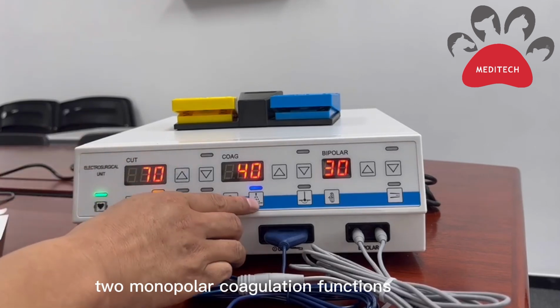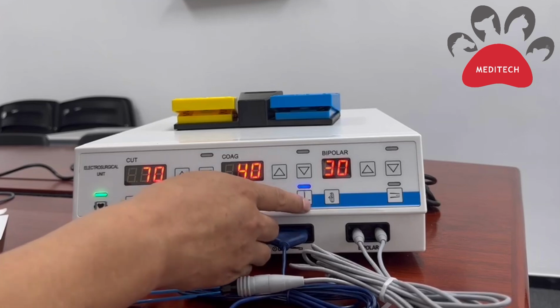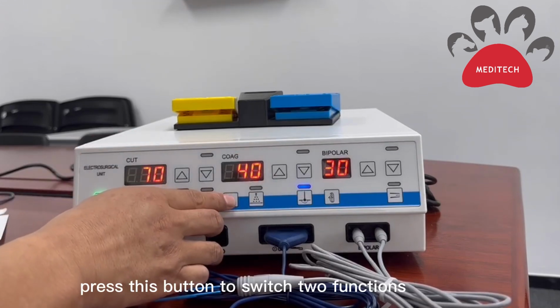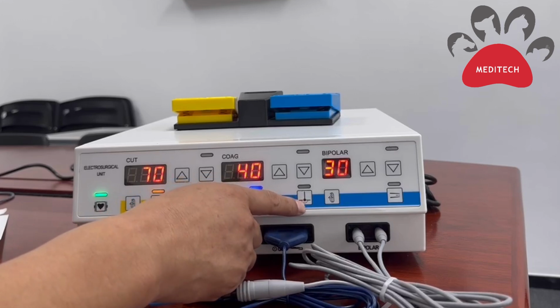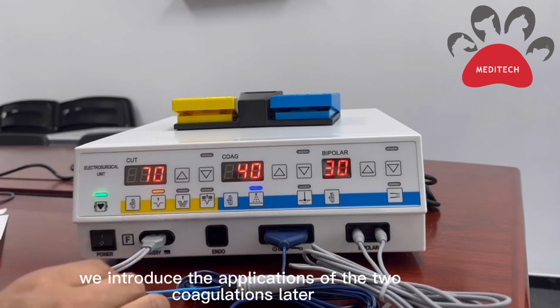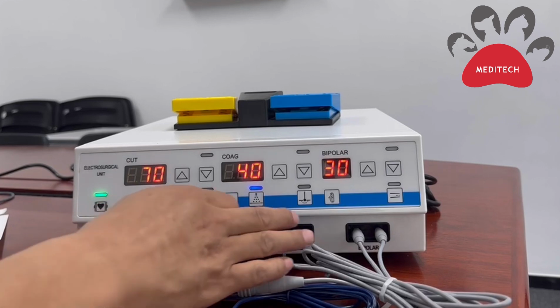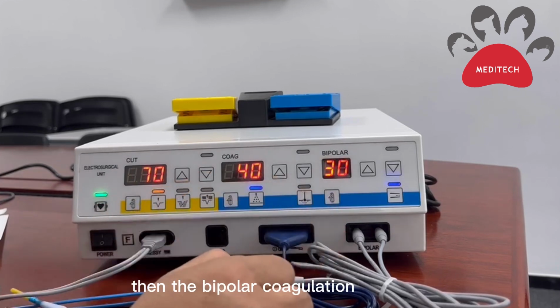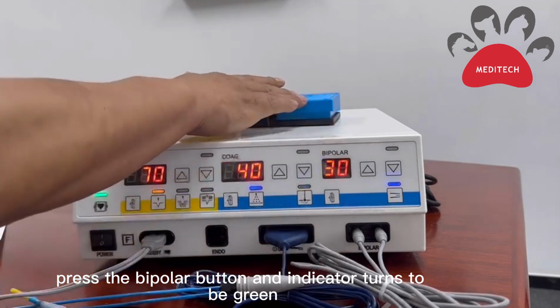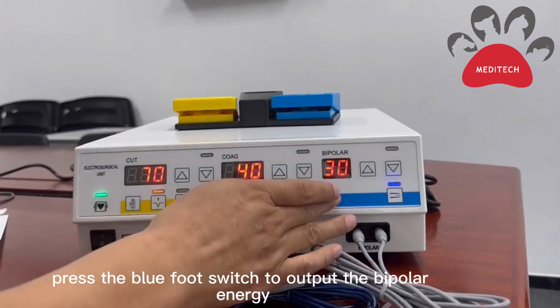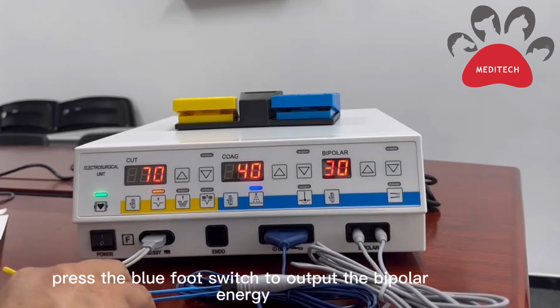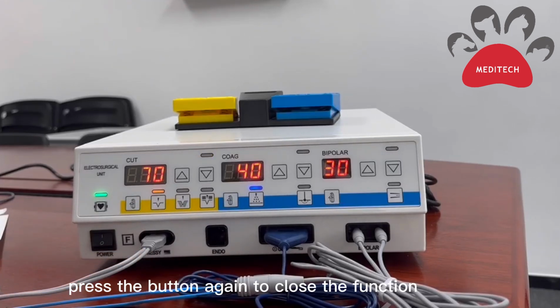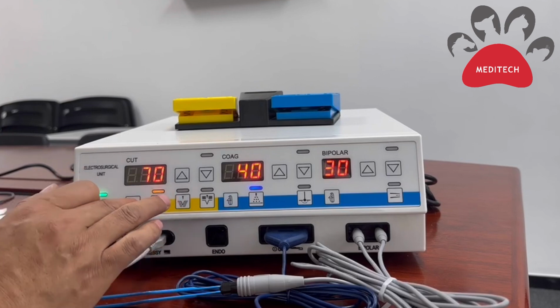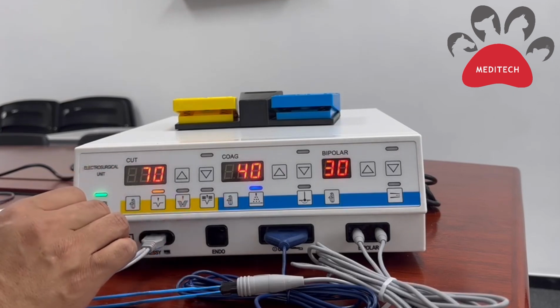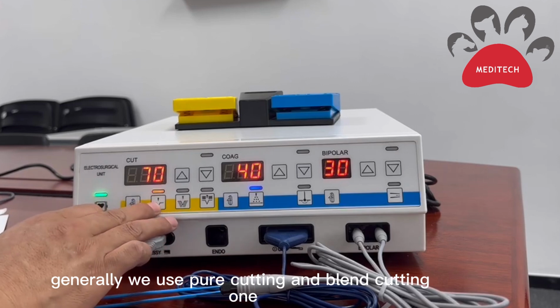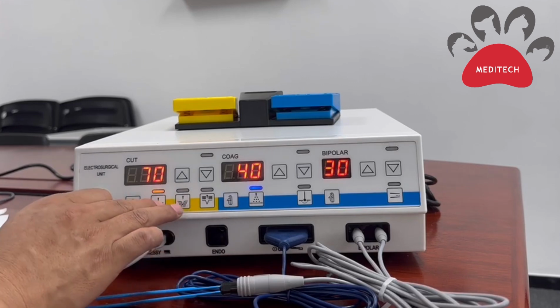There are 2 monopolar coagulation functions and soft coagulation. Press this button to switch functions. We will introduce the applications of the 2 coagulations later. Then the bipolar coagulation. Press the bipolar button and the indicator turns green. Press the blue foot switch to output the bipolar energy. Press the button again to close the function and switch to the monopolar mode. In surgery, generally we use pure cutting and blend cutting 1.